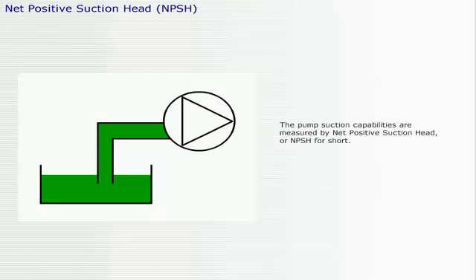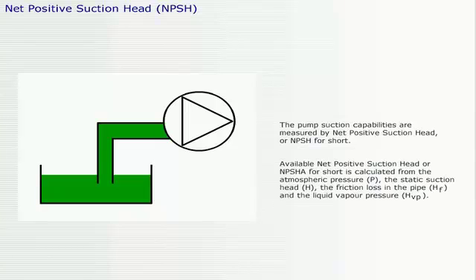The pump suction capabilities are measured by net positive suction head, or NPSH for short. Available Net Positive Suction Head, or NPSHA for short, is calculated from the atmospheric pressure, the static suction head, the friction loss in the pipe, and the liquid vapor pressure.